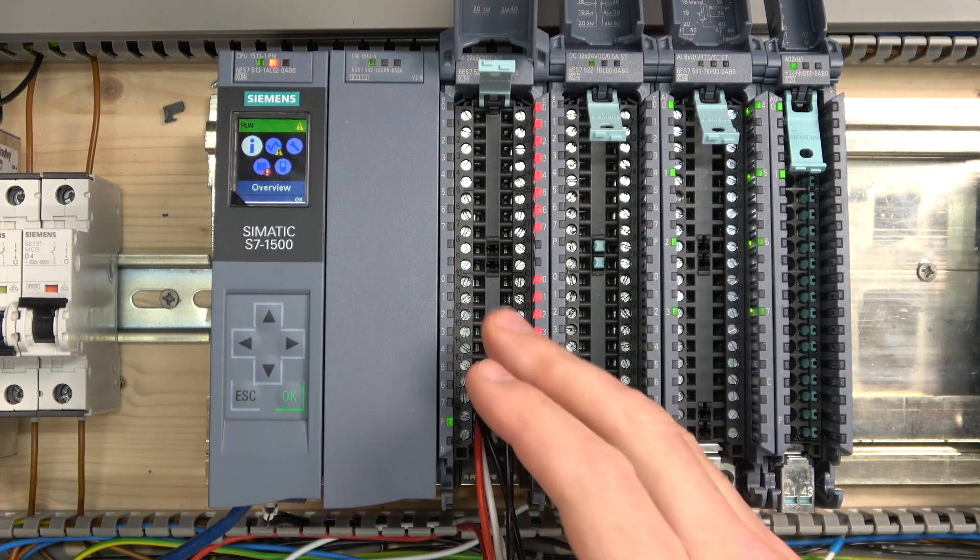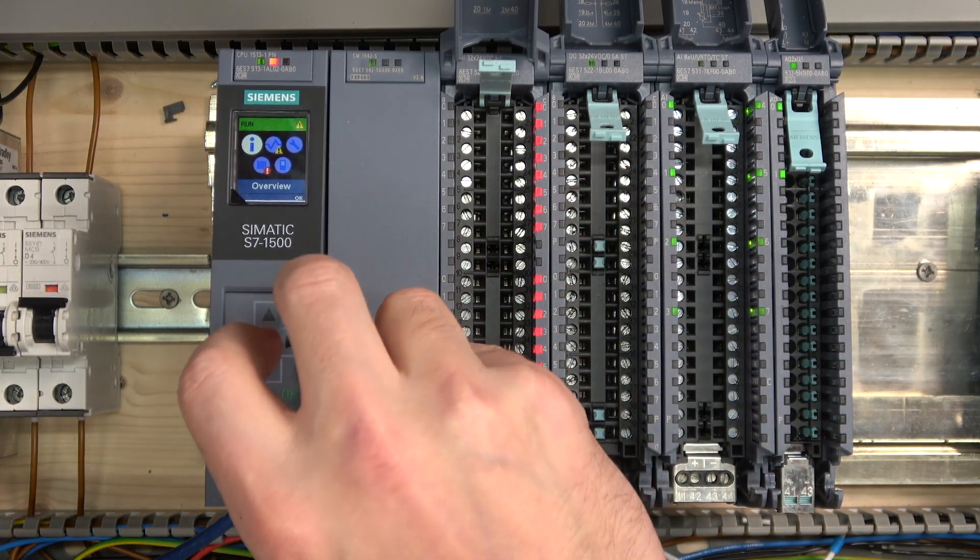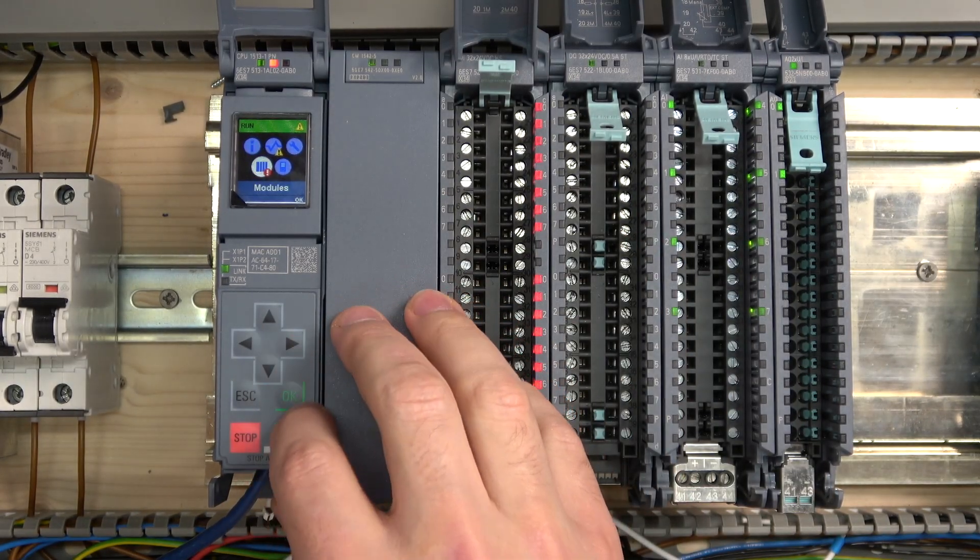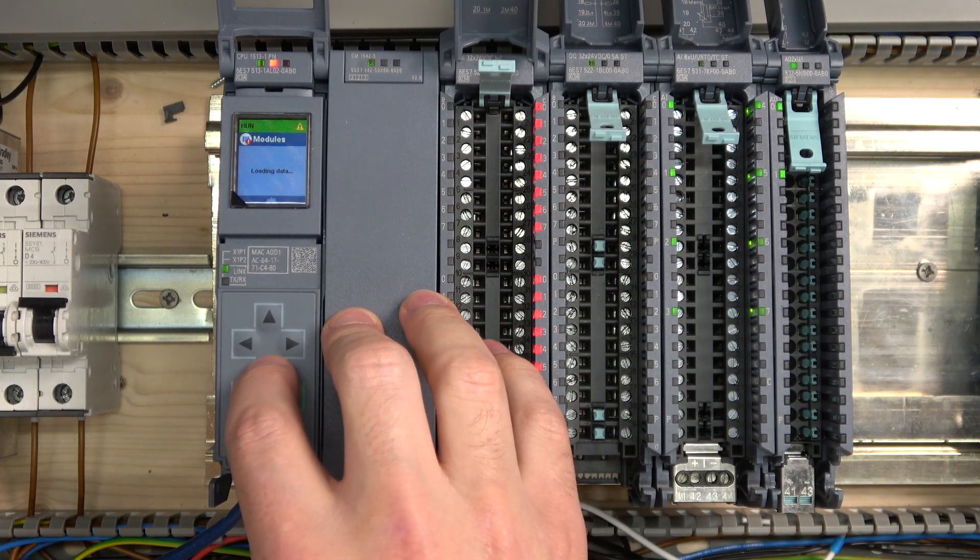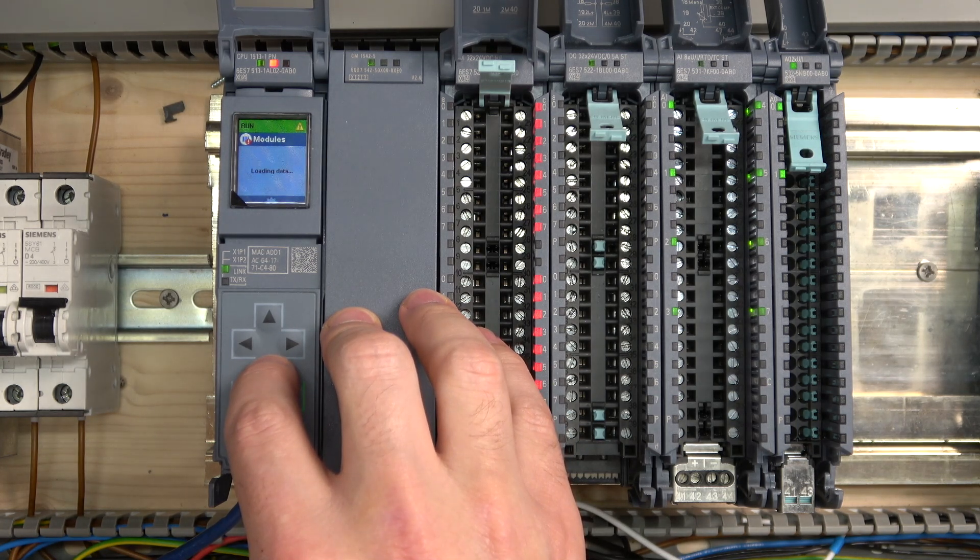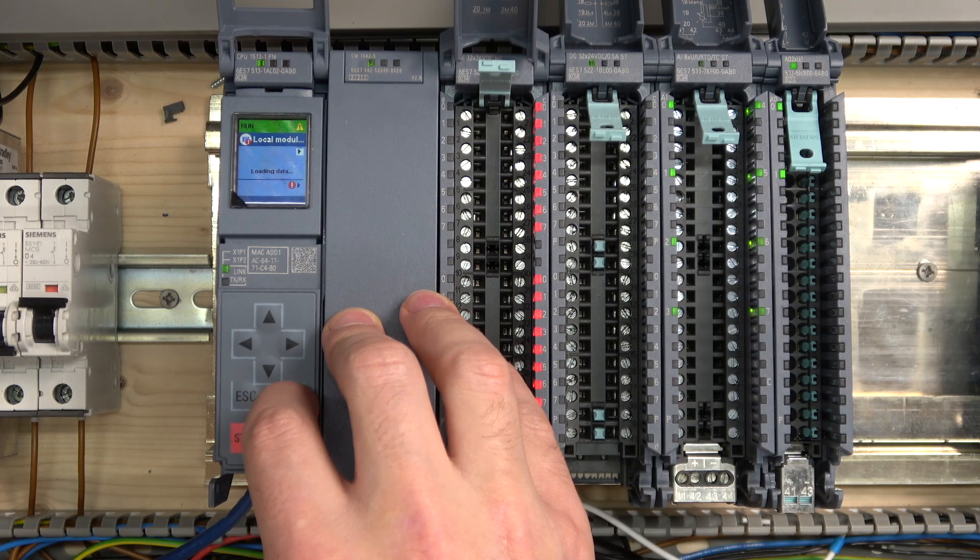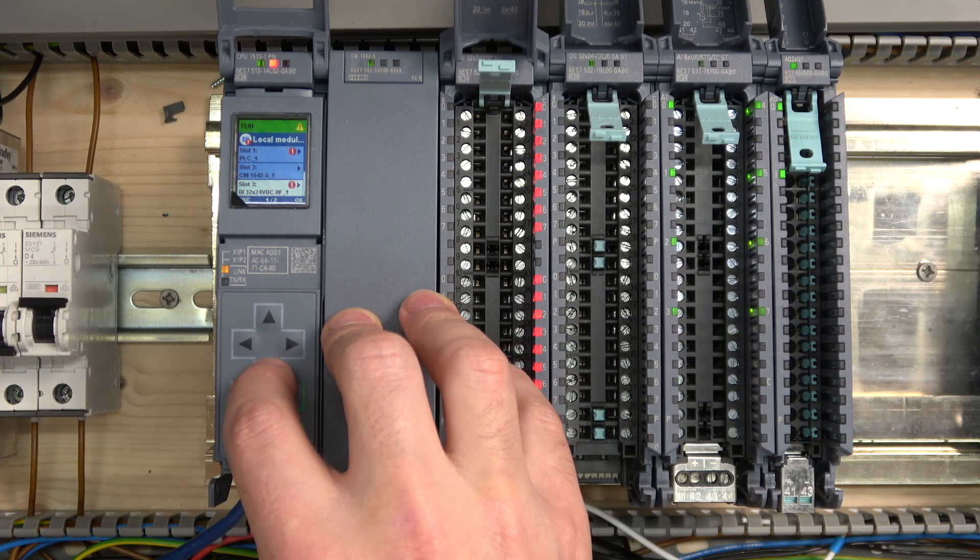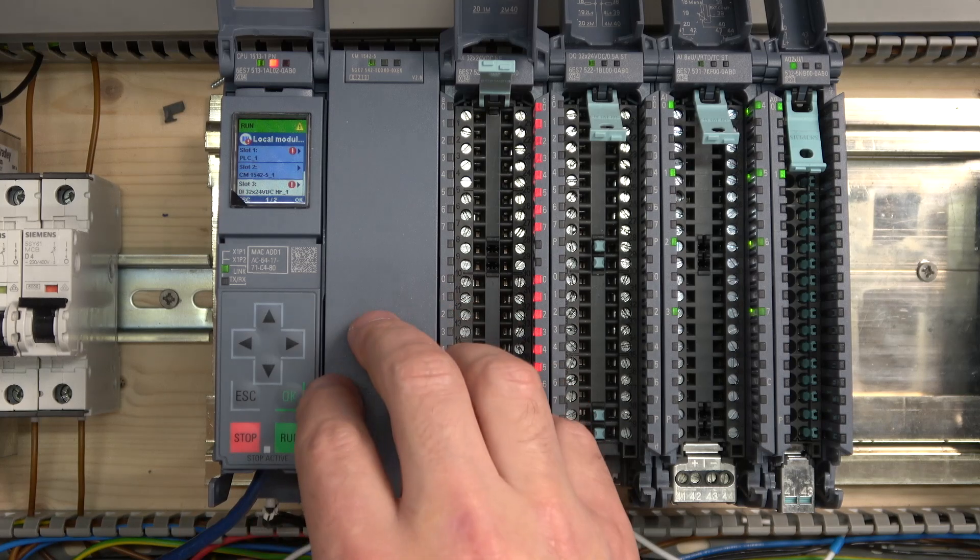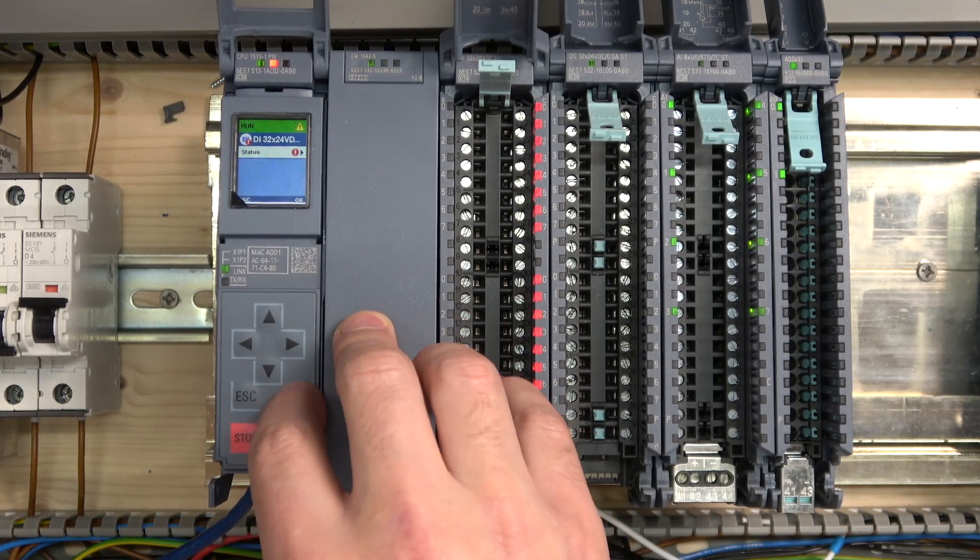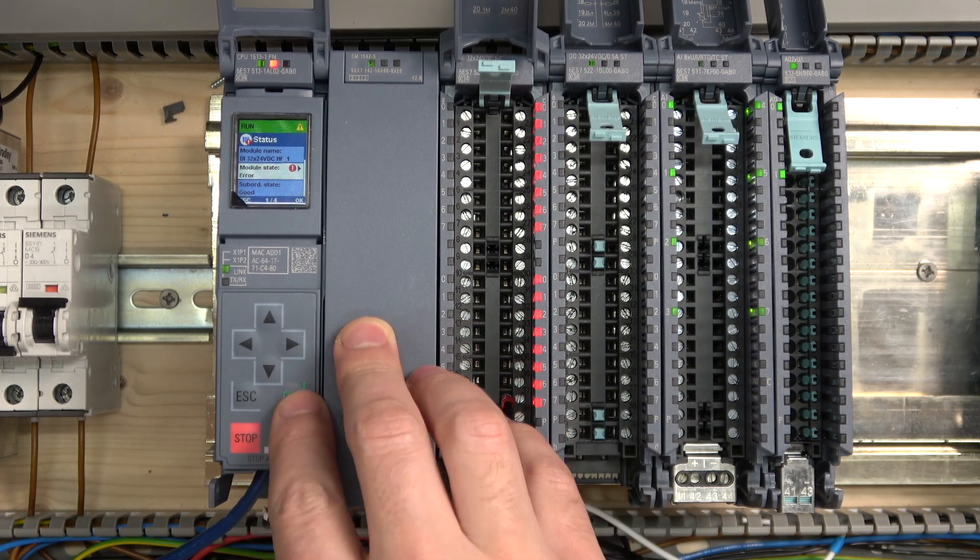And usually, if it's all been set up nicely in the actual diagnostics and in your HMI, it would indicate you exactly where it is. Let's quickly have a look at what does it say in here. Into the modules. Here we go, it goes in straight away, it tells you which, obviously slot one is obviously PLC, it's detecting there's an error, and it tells you exactly which slot as well. And if you click on it, if you have this option, you can click on it, look at the status, and module error. Let's have a look at this thing, it tells you where the error is.